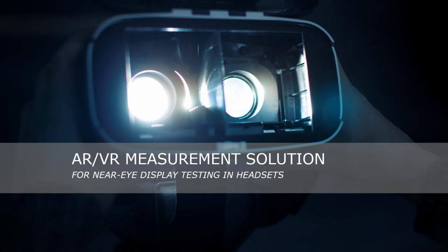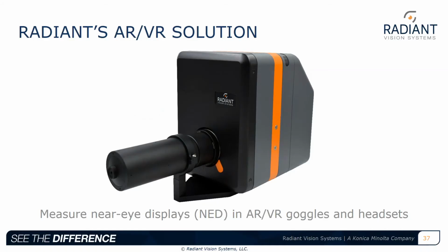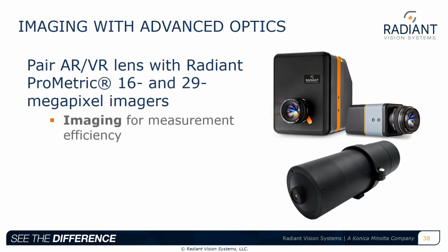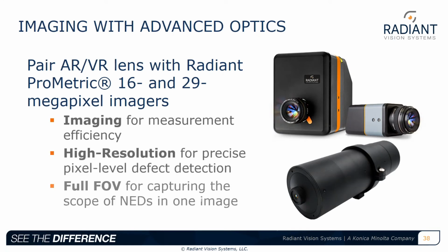Okay, so we have Radiant's solution. This is a Radiant eye camera with the near-to-eye lens, the AR/VR lens attached. The lens works with either the I16 or Y16 or I29 or Y29. For the full resolution, the 29 megapixel sensor is required because it's just simply a larger sensor. For color applications, the I camera is needed. If color is not important, then the Y camera is luminance or radiometric.